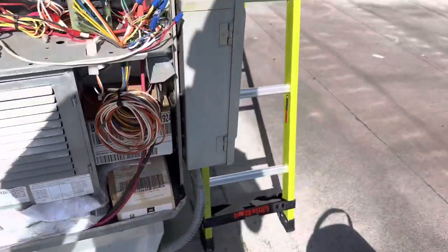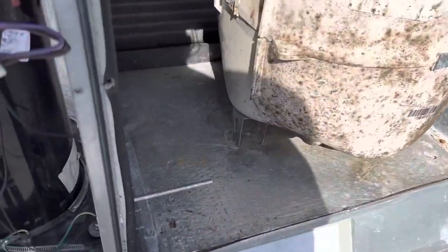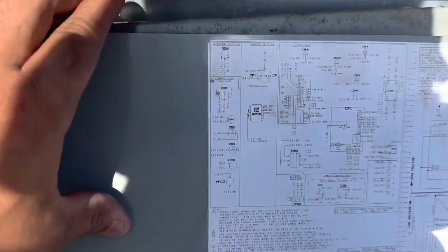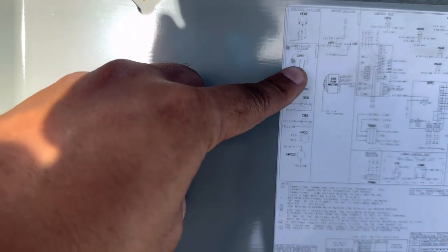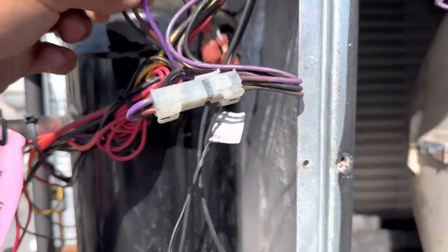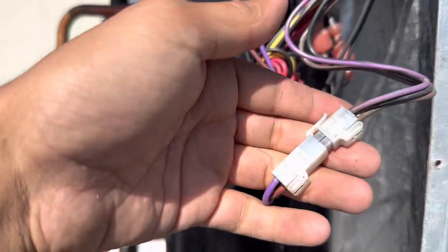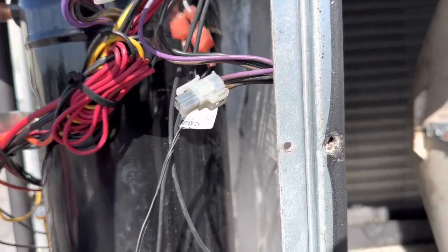First thing you want to do is shut off your disconnect downward and disconnect the wires from that. You want to find out which one that is — you can go to your schematic, go to the outdoor section, and see right here it says black, purple, brown, and black. So you would go through your wires — here's black, purple, and brown — and just disconnect it right here, push it upward and pull.